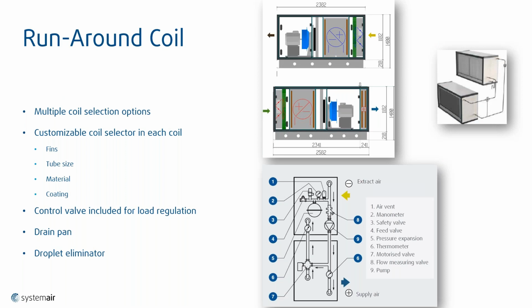Another energy recovery option is the runaround coil. Now, this assists us if you do have any clean rooms where you have to make 100% sure that you don't have any contamination of the airstreams, or you have your supply and exhaust in different locations, you can have the runaround coils installed as well. The energy recovery here does depend on the rows and fins that you have within the actual coils. So your efficiencies can be all the way up to 70–75%, but again, that means that you need a massive coil, which adds pressure drop. So this is a little bit of an older school technology, but it is nevertheless still available to you if you have those requirements.